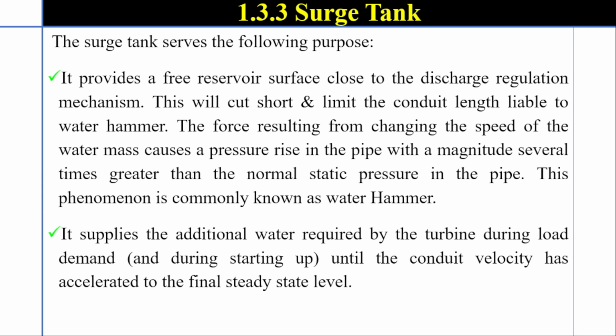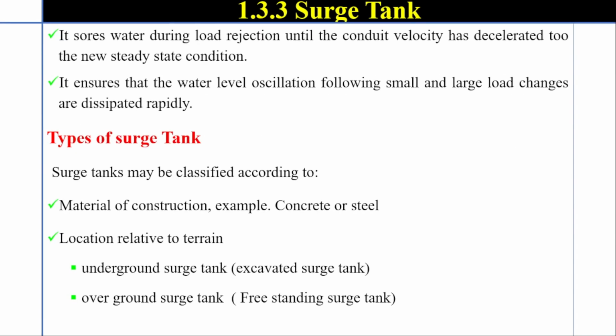It supplies the additional water required by the turbine during load demand or during starting up until the conduit velocity is accelerated to the final steady state level. It stores water during load rejection until the conduit velocity is decelerated to the new steady state condition. It assures that the water level oscillations following small and large load changes are dissipated rapidly.